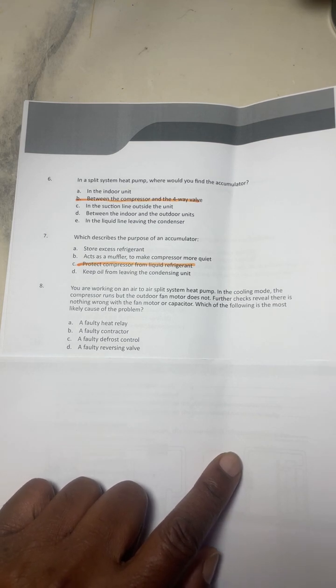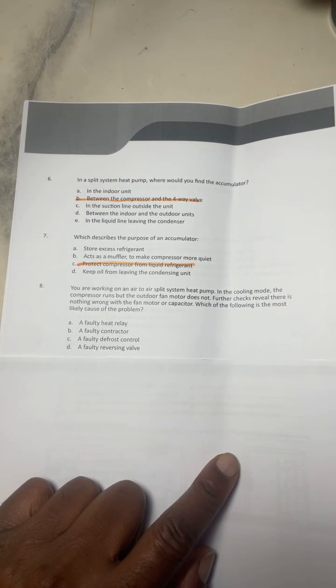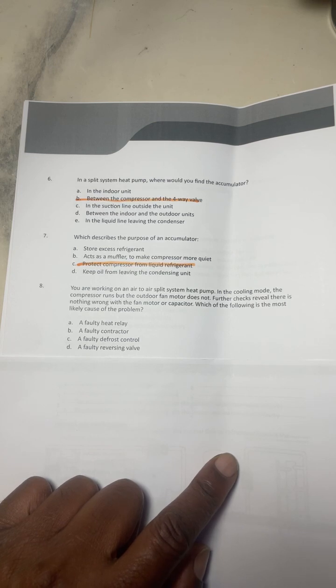You are working on an air-to-air split system heat pump. In the cooling mode, the compressor runs, but the outdoor fan motor does not. Further checks reveal there is nothing wrong with the fan motor or the capacitor. Which of the following is the most likely cause of the problem? A, a faulty heat relay. B, a faulty contactor. It says contractor, but it should be contactor. Or C, a faulty defrost control. D, a faulty reversing valve. Number 8, faulty defrost control.